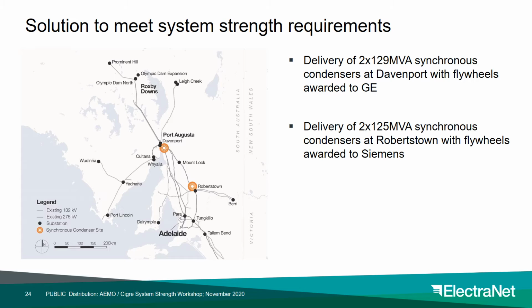Tendering was undertaken and delivery of two 129 MVA synchronous condensers with flywheels was awarded to GE for Davenport. Subsequently, further tendering was performed for the Robertstown site, and Siemens was awarded the contract to deliver two synchronous condensers with flywheels at the Robertstown site. All four synchronous condensers will have flywheels providing inertia of 1100 megawatt seconds per synchronous condenser, or a total of 4400 megawatt seconds of system inertia, which meets the minimum inertia shortfall declared by AEMO.